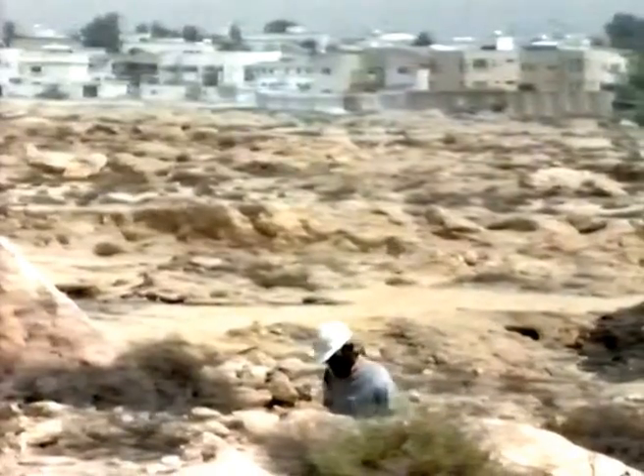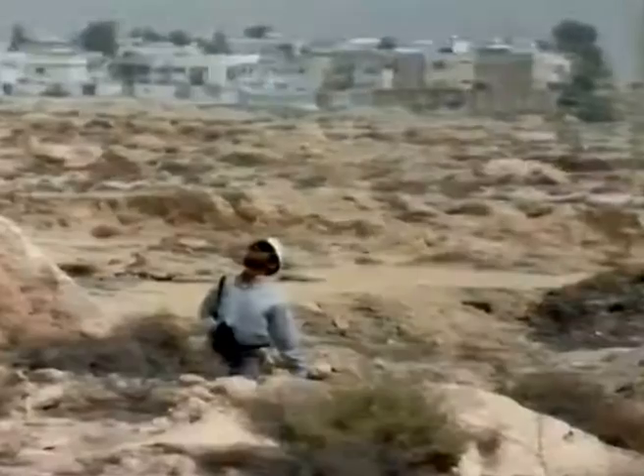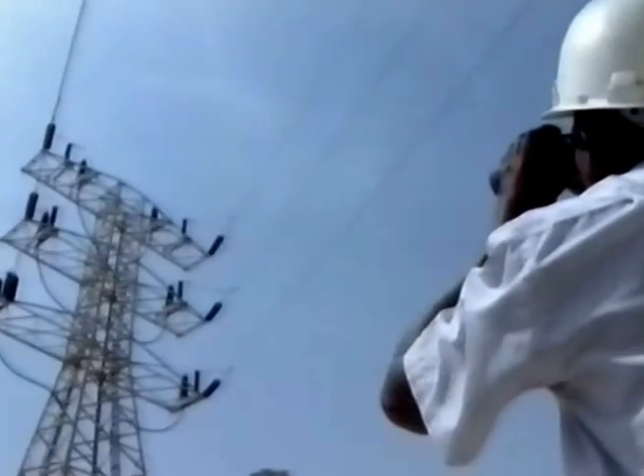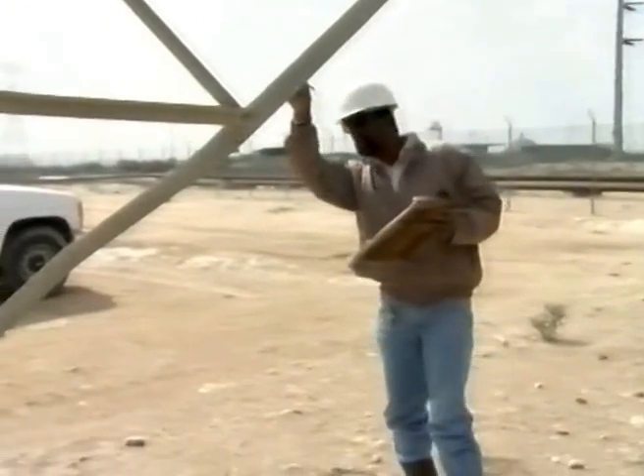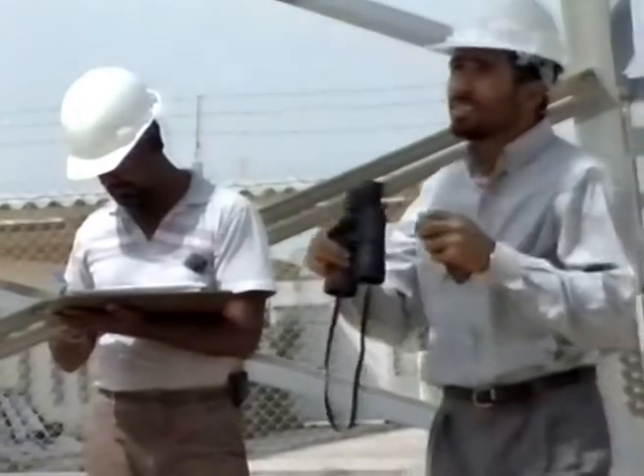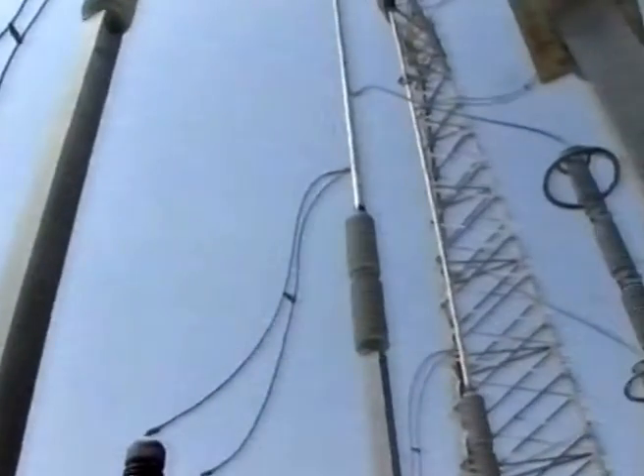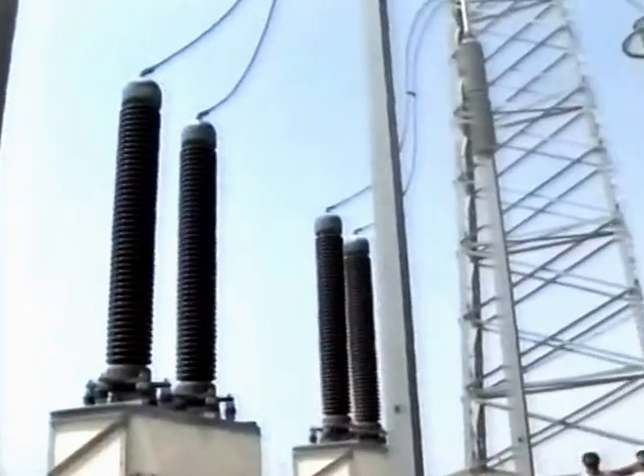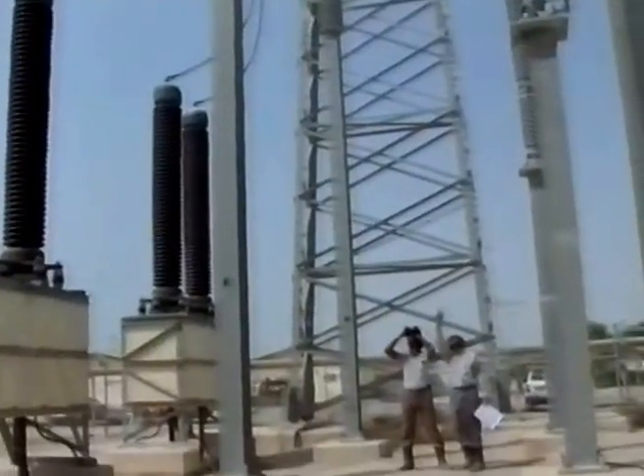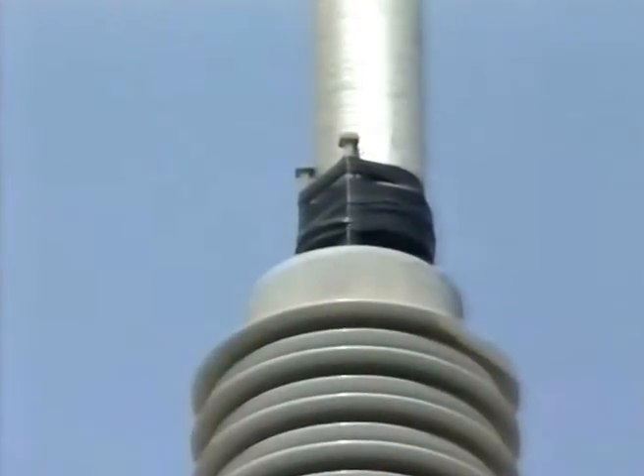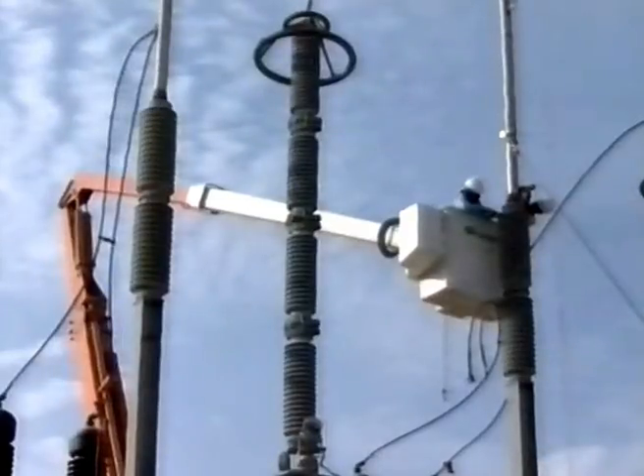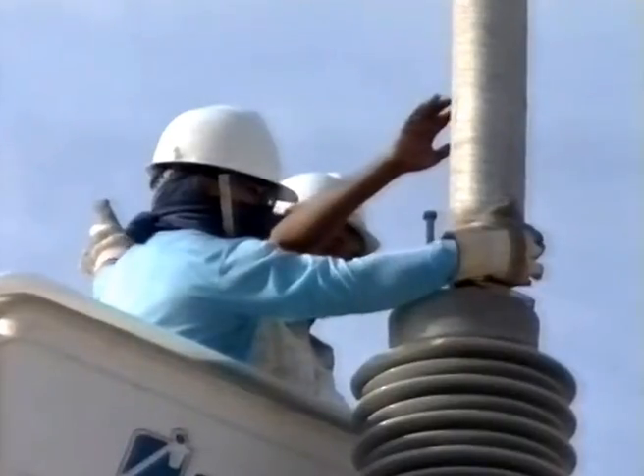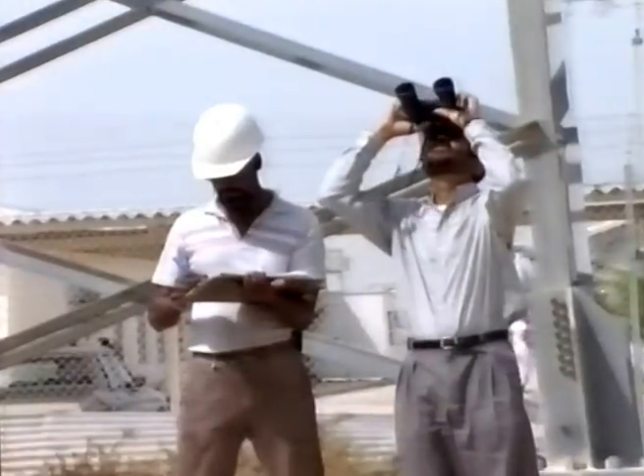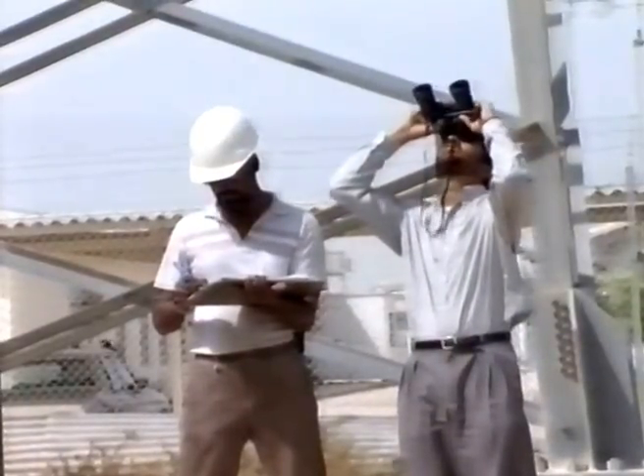All overhead transmission lines are to be inspected by a surface patrol without climbing or using any aerial device. The inspection shall be done once every 3 months. There are some exceptions, however, as to the following. Lines unable to be returned to service due to faulty line apparatus shall be patrolled immediately. In this instance, quickly look for major damage. If the faulted line can be returned to service as soon as possible after tests, these shall be patrolled the next working day.